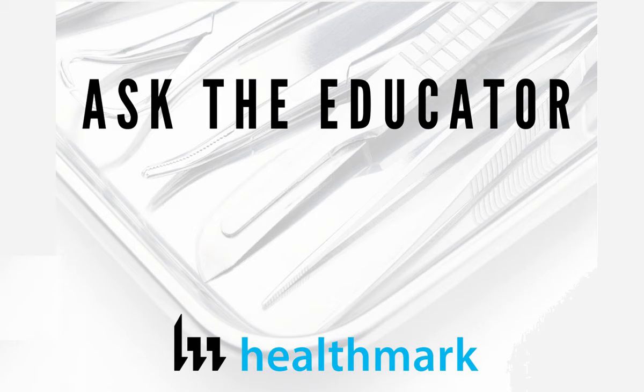This is something we've been aware of for years, and it's been a citation for years: the dilution for detergent used in manual cleaning matters. We've seen people say, I use 2 pumps. The next staff member says I use 3 pumps. The next says 4 pumps. You ask them how much water they're putting that detergent into. Well, I was taught to fill it up to the top. How many gallons is that? I don't know, I was just taught to fill it up to the top. So you need to make sure your dilution is correct.